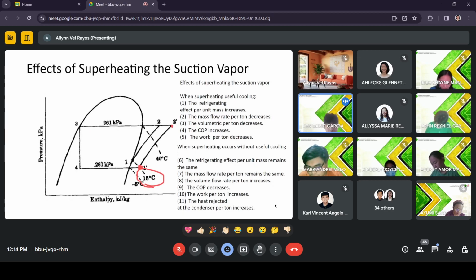Now, when superheating occurs without useful cooling, the refrigerating effect per unit mass remains the same. The mass flow rate per ton remains the same. The volume flow rate per ton increases. The COP decreases. The work per ton increases. The heat rejected at the condenser per ton increases.